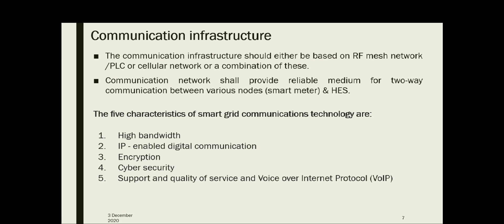Communication infrastructure is one of the main parts of an automatic meter infrastructure. It should be based upon a radio frequency mesh network, power line communication or PLC, a cellular network, or a combination of all these. The communication network shall be based on suitable standards prescribed by IEEE or IEC. It shall provide a reliable medium for two-way communication between various nodes — not just from smart meters to the utility, but also with the consumer.